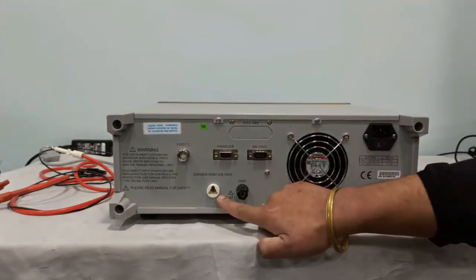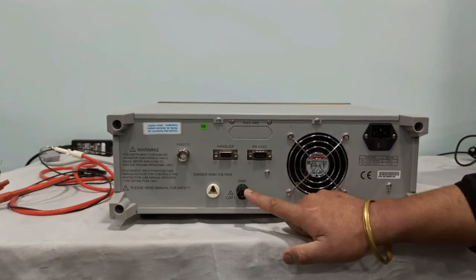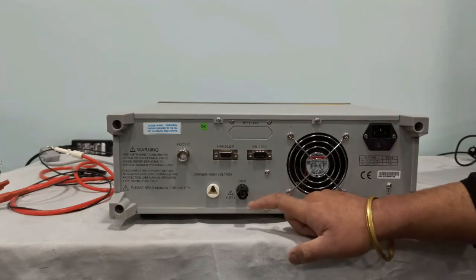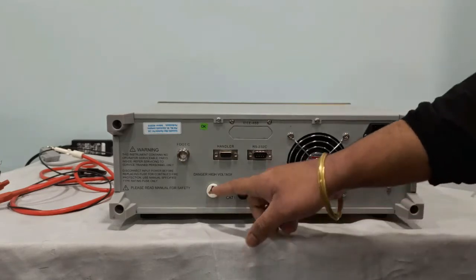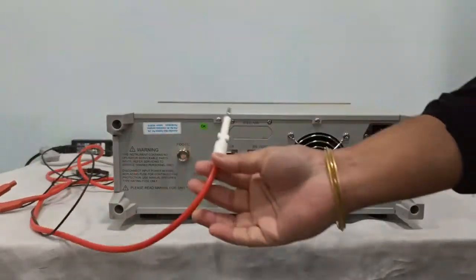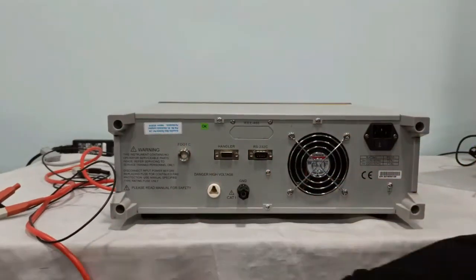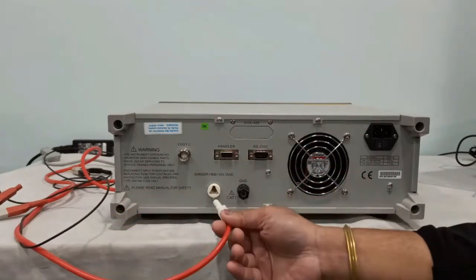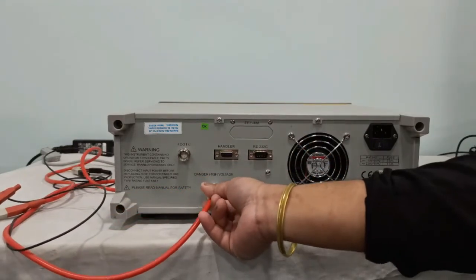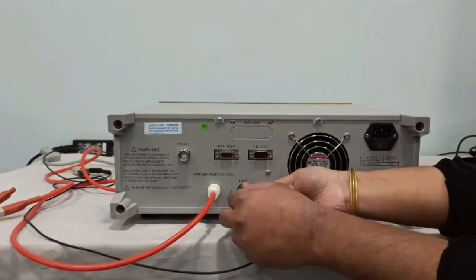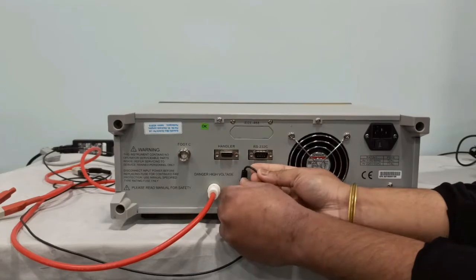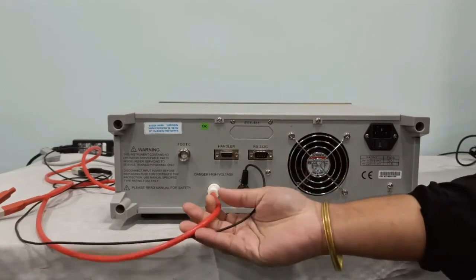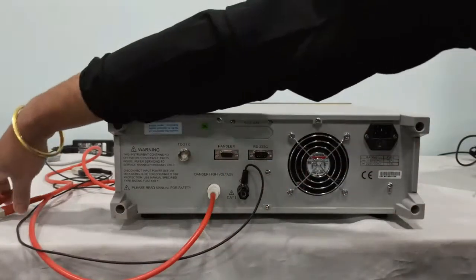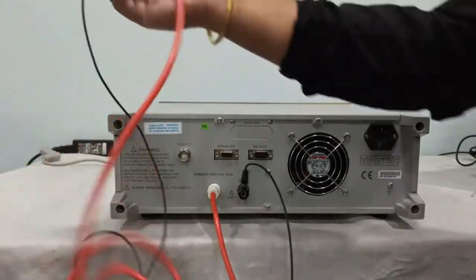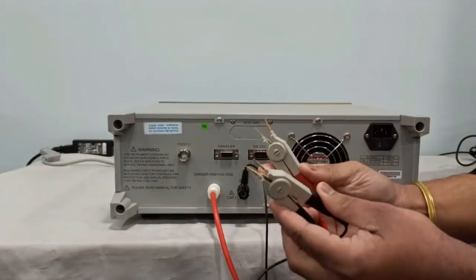Now this is the HV test terminal and this is the ground test terminal. We have the high voltage cable plugs in these two ports. So this red cable goes into this HV test terminal and black cable is connected to this ground test terminal like this. So this is how cables are connected, and DUT will be connected across these two terminals.